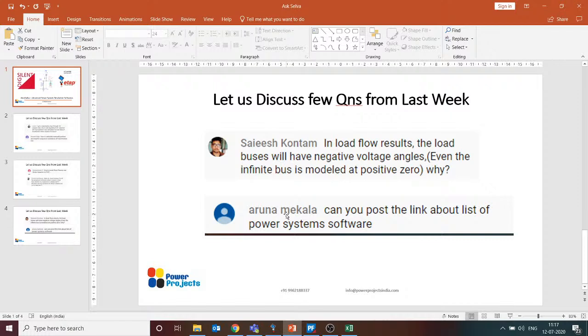So, considering the losses in the transformer, etc., if your system power factor is more than 0.8, or if you have over-designed your generator capacity, you need not really worry about reactive power compensation or power factor correction using capacitors. Your generator itself has the capability to meet the reactive power demand of the loads. If the reactive power demand from the loads is higher than your generator's reactive power capability, then you need to think of capacitor banks. Hope that answered your question, Parthiban.